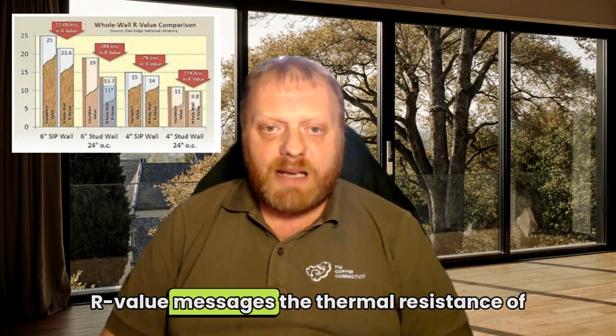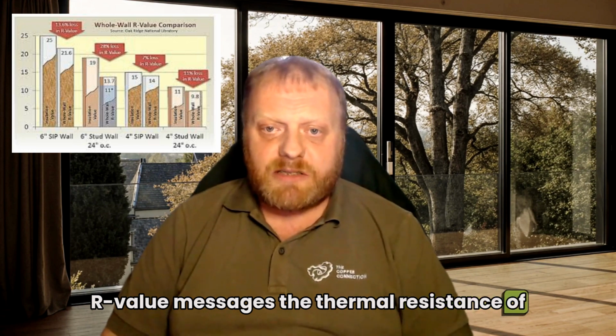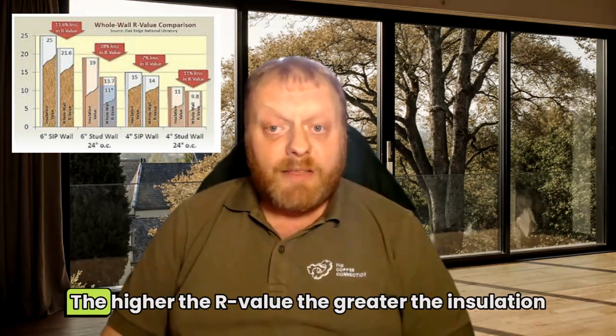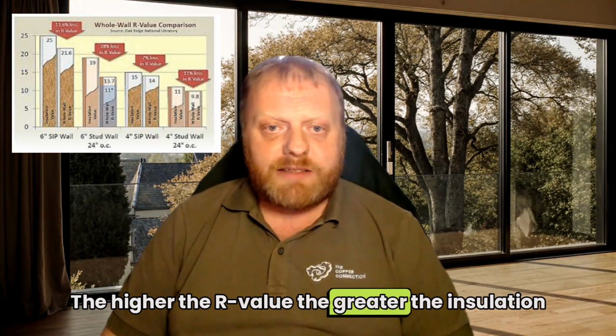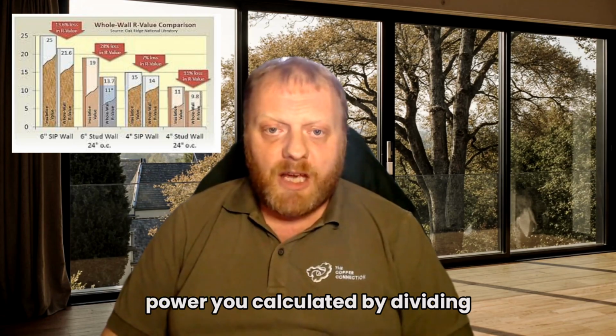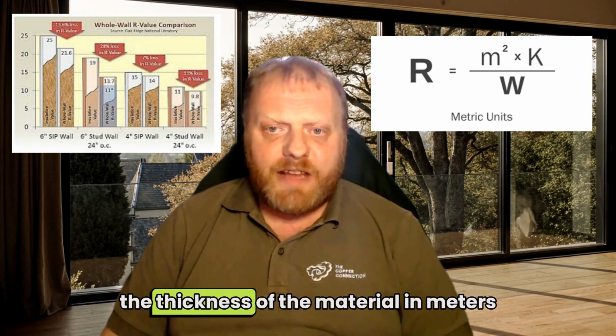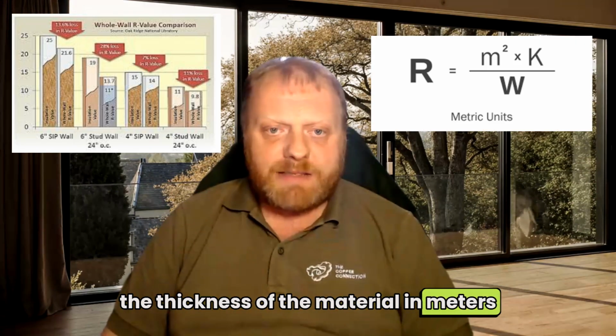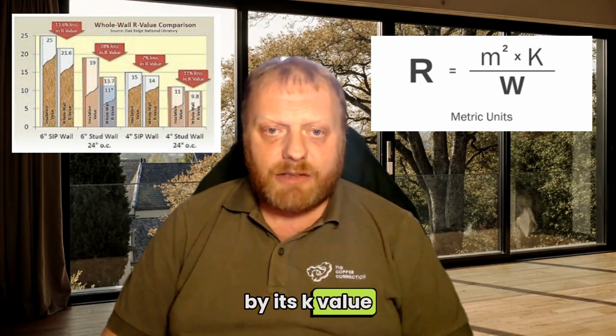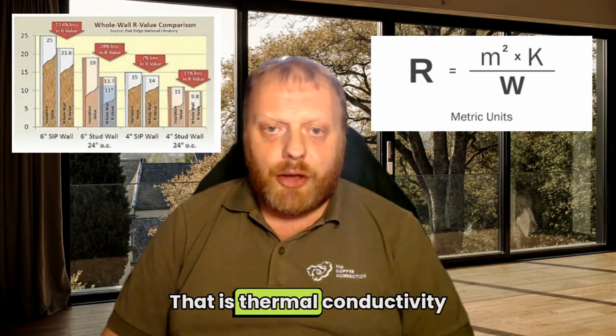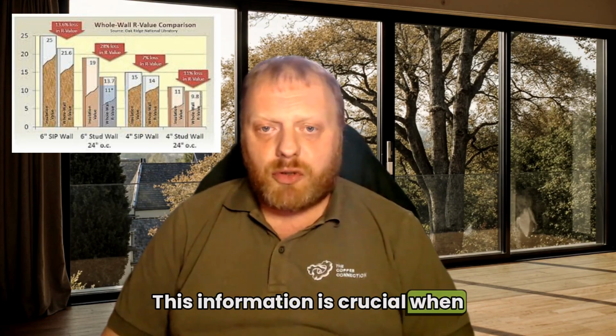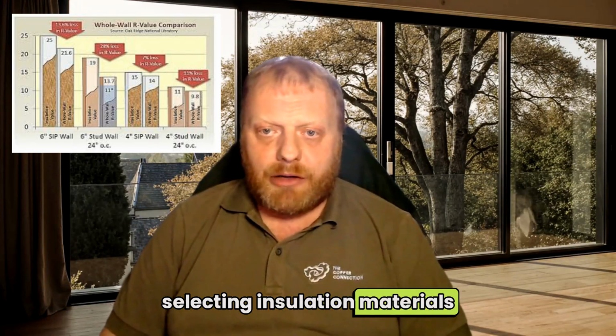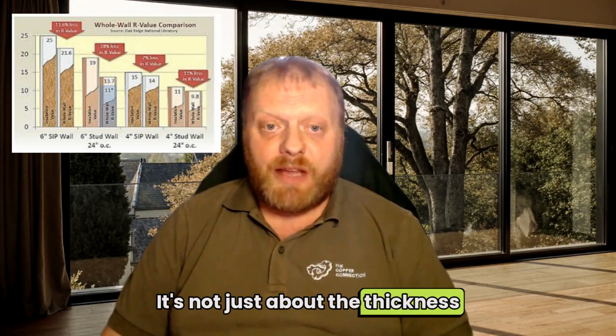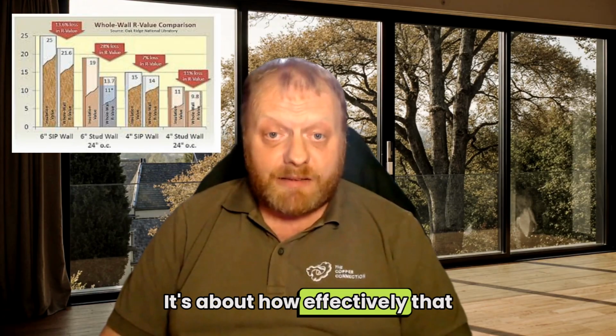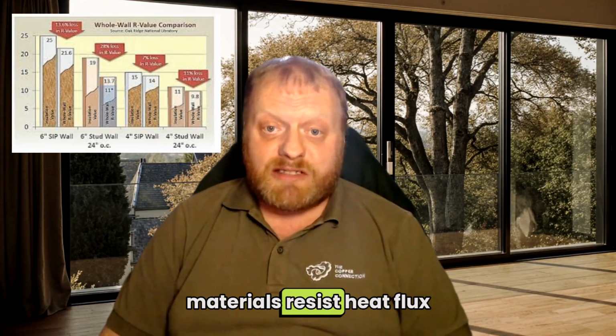The R value measures the thermal resistance of a material. The higher the R value, the greater the insulation power. You calculate it by dividing the thickness of a material in metres by its K value. That is thermal conductivity. This information is crucial when selecting insulation materials. It's not just about the thickness, it's about how effectively that material resists heat flow.